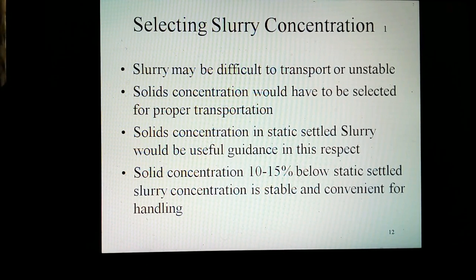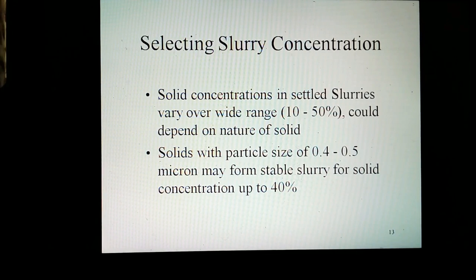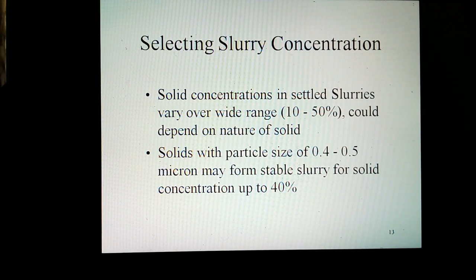Solid concentration of slurry becomes an important consideration for the following reasons. Solid concentration governs the slurry's specific gravity and hence pumping costs, and sometimes the rheology of the slurry. At certain solid concentrations, slurry may be difficult to transport or unstable. In such situations, solids concentration would have to be selected for proper transportation. Solid concentration of static settled slurry would be a useful guidance. Generally, solid concentration 10 to 15% below static settled slurry concentration would prove stable and convenient for handling. Solid concentrations in settled slurries could, depending on the nature of solid, vary over a wide range of 10 to 50%. Solids of particle size 0.4 to 0.5 micron are stable for solid concentrations up to 40%.